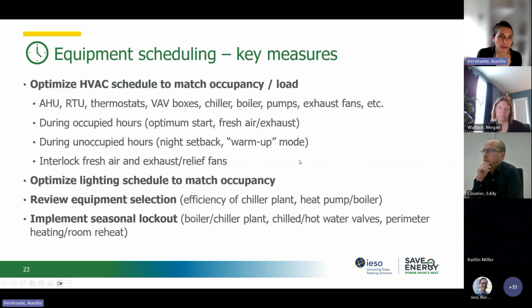So to summarize, for the equipment scheduling opportunities, first you want to optimize the HVAC schedule to match occupancy and load during occupied hours and during unoccupied hours. Maybe you want to interlock fresh air and exhaust relief fans to prevent them from running after hours. You want to optimize the lighting schedule to match occupancy, maybe review equipment selection and implement seasonal lockouts as we discussed.